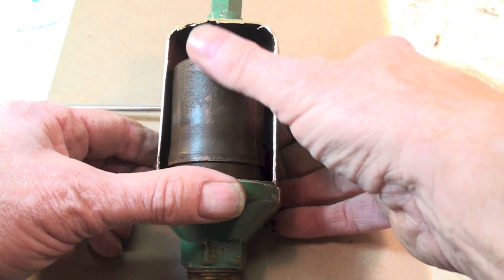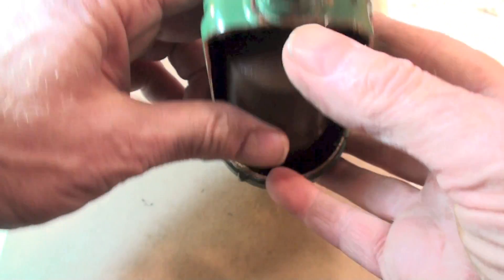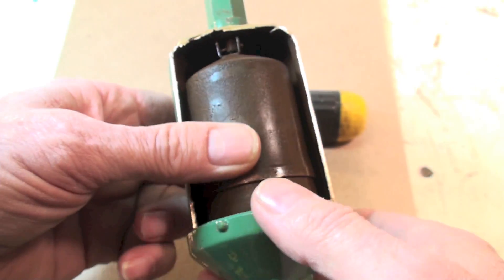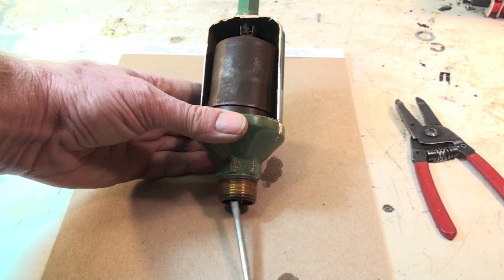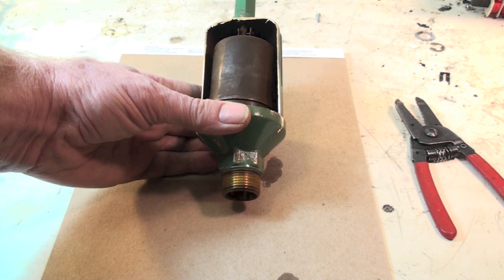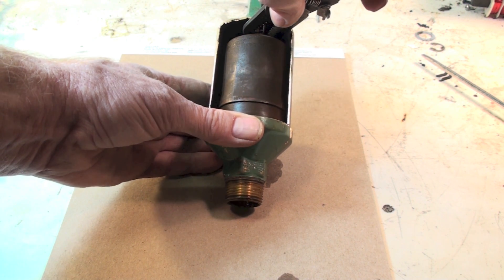They make a little tiny one — I think it's called the Hoffman 67 — that you see commonly on small units, but they both work the same. This float, when it goes up, it closes off a valve here. Water comes in the bottom, and air bubbles will come in as they go through the pipe. Normally the flow will be up, and that will close the valve on the top.